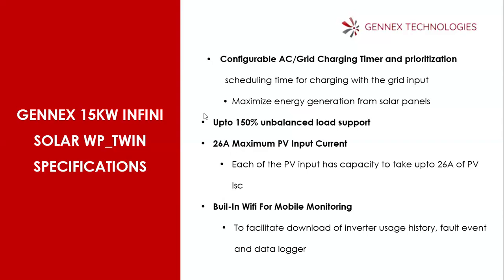Actually, if we are using any three-phase system, you divide the total power by 3. So if you are using 15 kilowatts now, each of the phases has 5 kilowatts. So if you now have more than 5 kilowatts on one phase, it will not affect the inverter, which means you can have up to 10 or 13 kilowatts on one phase, if the other phases are idle. So the inverter supports that.